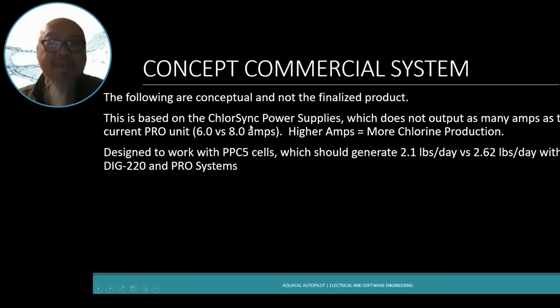Based on the ChlorSync power supplies, which don't output as many amps as a current AutoPilot Professional, we're looking at a difference of 6.0 amps versus 8 amps. Higher amperage produces more chlorine, so the ChlorSync system will produce 2.1 pounds per day versus 2.62 pounds per day for the old digital and Pro system.